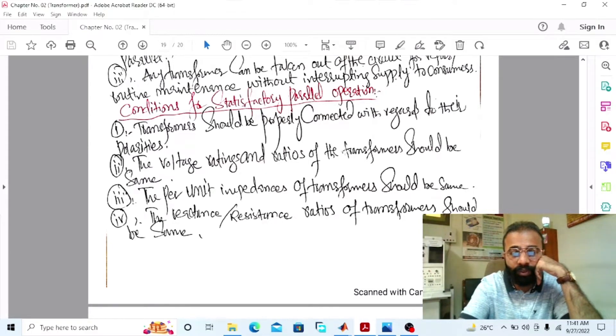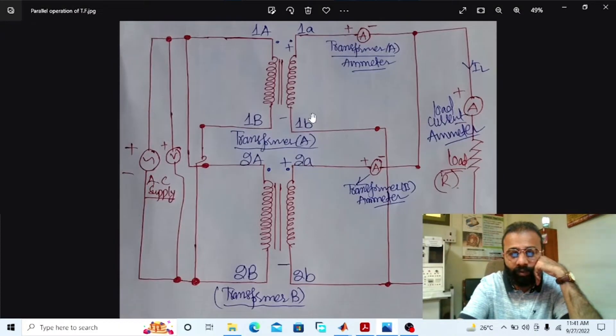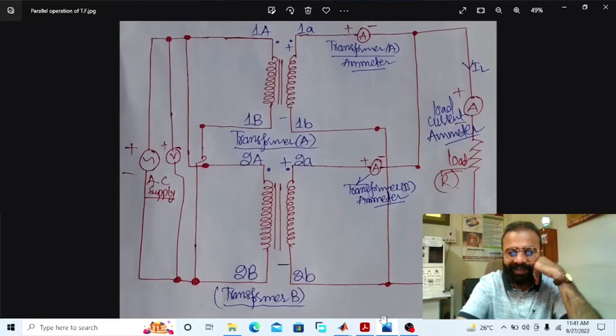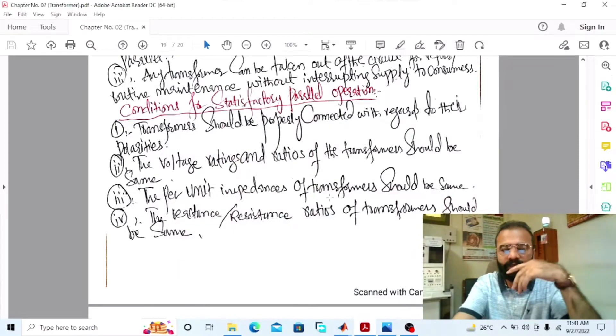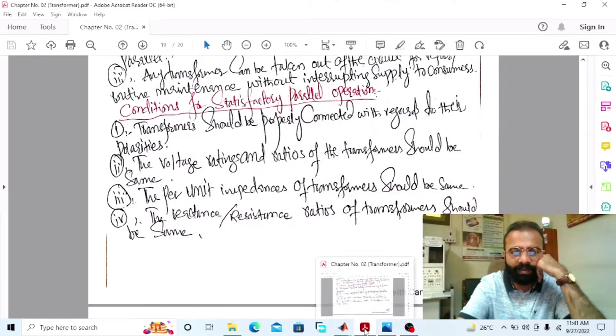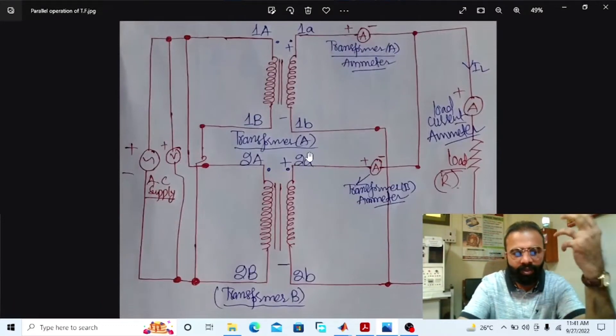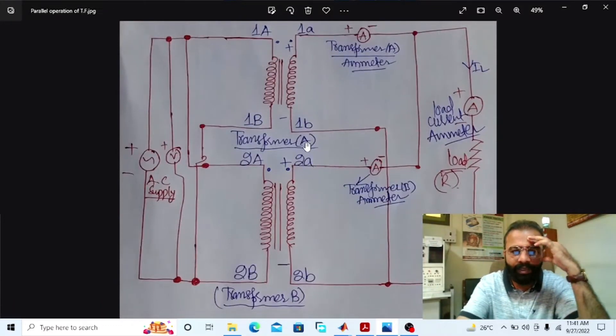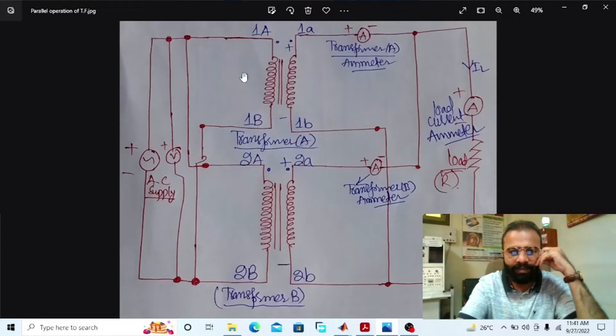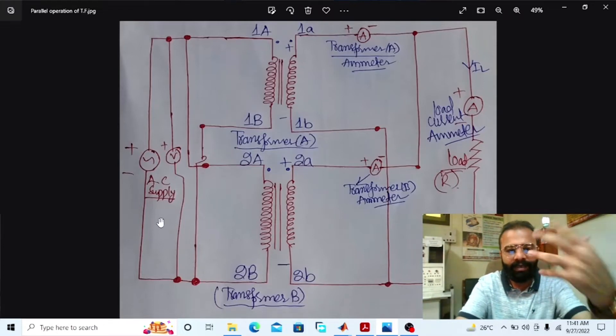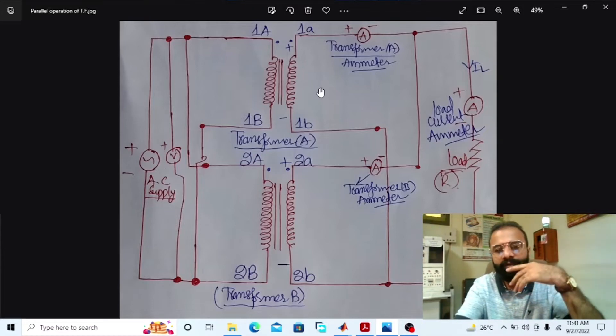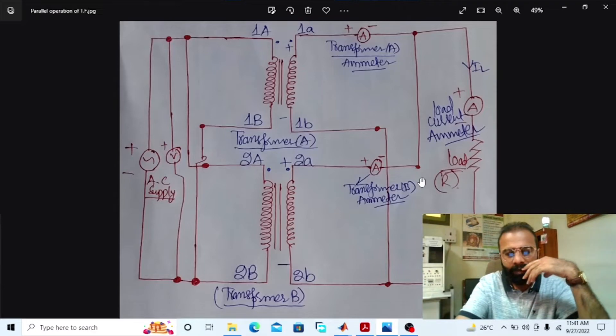The voltage ratings and voltage ratios of both transformers should be the same. The transformers are connected according to their same polarities. The per-unit impedance of the transformers should be the same, and the reactance-to-resistance ratios should also be the same. When connected in parallel, terminals of the same polarities are joined to the same busbars, with primaries connected to supply busbars and secondaries to load busbars.